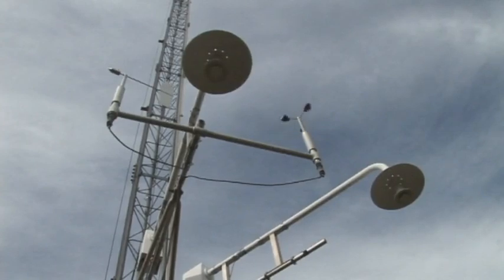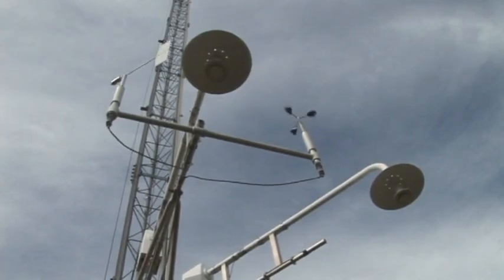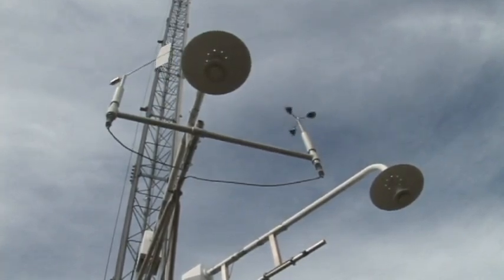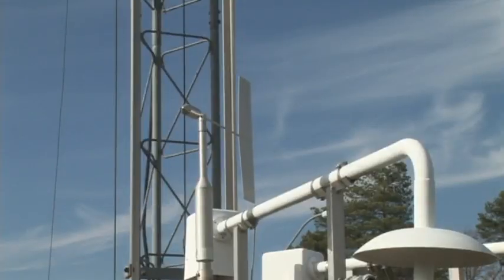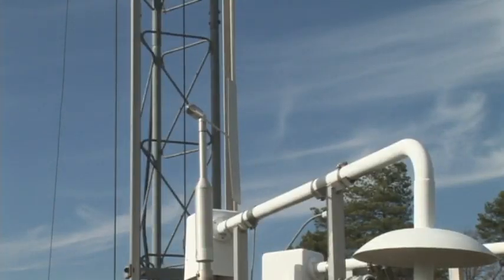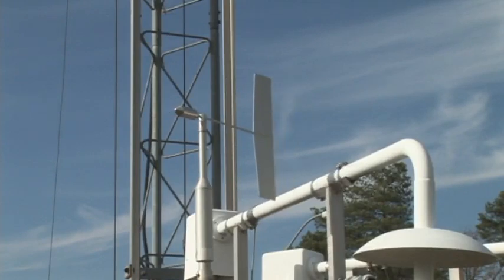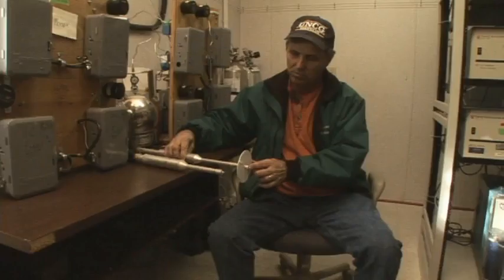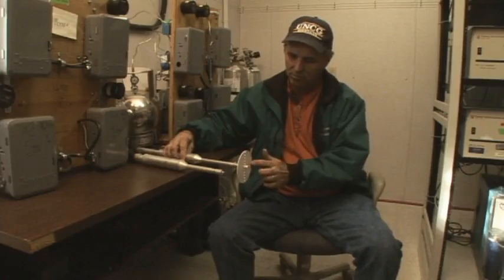As we discussed earlier, all direction sensors have bearings that we refer to as a starting threshold. This is the amount of force, that is wind, that is needed to overcome the resting inertia to get the sensor moving. As bearings age, the resting inertia will increase. It is critical that the torque test be performed every time the calibration is performed. Note that the starting threshold of a wind direction sensor will be different from the wind speed sensor threshold.